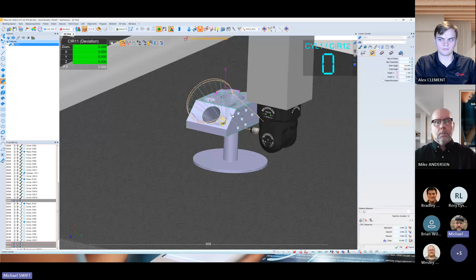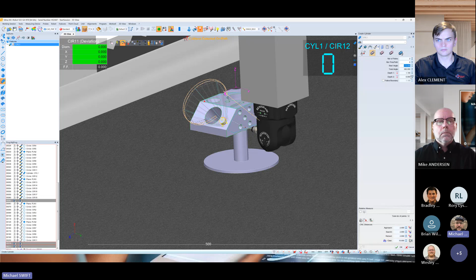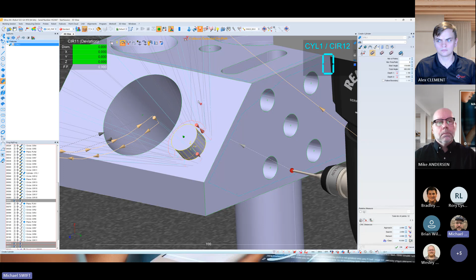So great, found a collision, and I can solve for it manually, or I can let the software solve for it. But before I solve for it, what I like to demonstrate here is that I may want to change some of the parameters of how we are measuring the cylinder, right? Maybe I want to take 4 probings instead of 6 around. I could do that. I could change the start and end angle. I can measure 180 degrees, 92 degrees. I can, of course, do any of that. I also might want to adjust the depth of the feature measurement. So maybe I want to start 1.1 millimeter from the top perpendicular surface, and then on my second band, go 6.9 millimeters from the top surface. Maybe I'll shorten that up a little bit to 5 millimeters. Sure, I can do that. And there's a few more options.